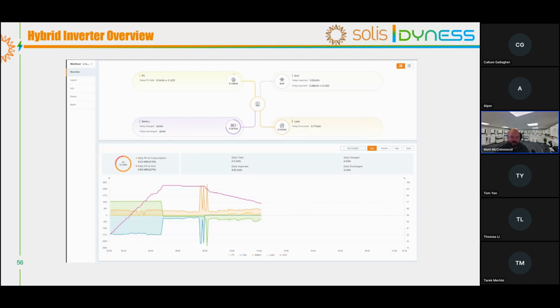Best things to maybe look at are, for example, the energy imported and exported values. If they were worried about how the system's performing, they can actually see that through the day. But for a general snapshot, it's not worth worrying about, in my opinion. At the bottom of this screen, it shows you the load profile. Because we can monitor what the grid point's doing because of the meter, we can do calculations to say what the load is. So if we know that you're exporting 1 kilowatt, but you're producing 3 kilowatts, then the load must equal 2 kilowatts, for example. So that's how that calculation is done. It's by knowing what the PV is generating and what the grid's doing by importing or exporting. You can then calculate what the load is.